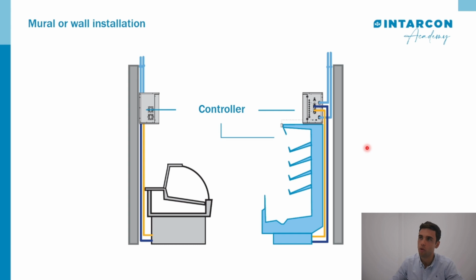That could be mural wall installation, and one of the key advantages of these units is the flexibility of assembly, because you can install in two ways: anchored on the wall, allowing for simple distribution of the facility and access for maintenance, or on top of the refrigeration service, optimizing space and reducing the distance between connections.